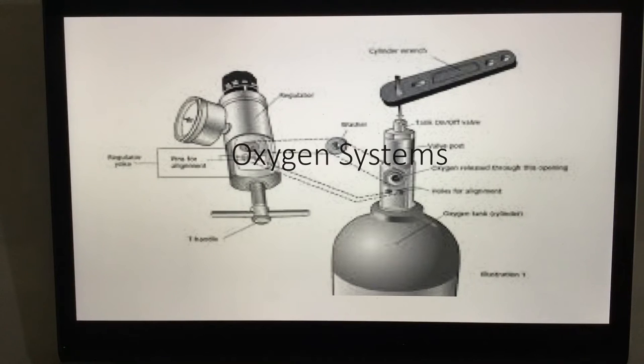There are many different sizes, but the valve to these tanks are very specific as it has a pin and index system. These oxygen tanks should be kept in their carrying devices or laying flat. We want to avoid using any petroleum-based lubricants and keep the oxygen away from anything flammable or any open source of flame.